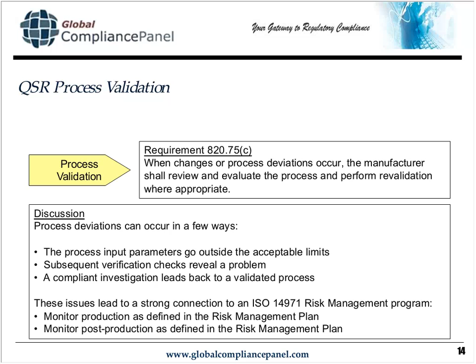Here's a couple of ways this problem could occur. We'll see a strong connection to the ISO 14971 risk management program. Often, processes are used on the manufacturing floor to control things that could present risk to users and patients if they were not under control. So production is one of the things we want to monitor in the risk management plan, and post-production—complaint investigations, for example—may also lead us back into validated processes.